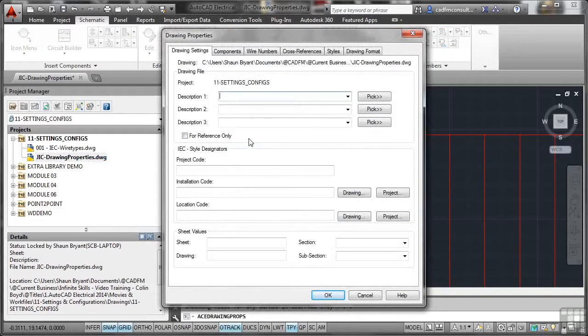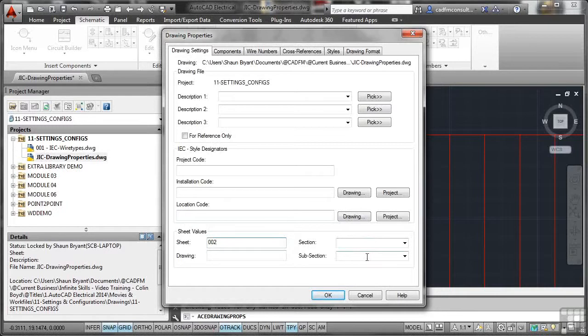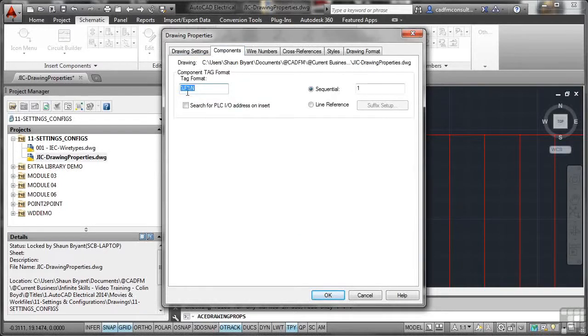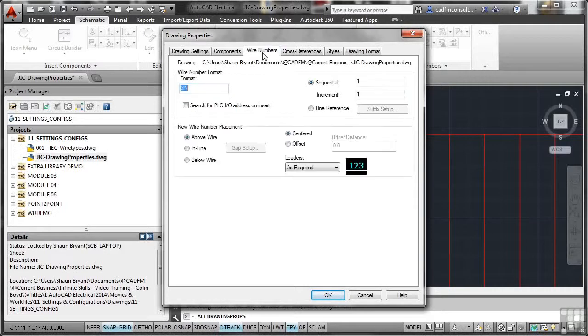In the drawing settings you've got project, description one, description two, project code, installation code, and location code. We'll give it sheet 002 since it's next in the drawing list. Section and subsection are extra descriptor fields for database work. On the components tab, you'll see the component tag format: %f, %n — that's the numbering format, currently sequential starting at 1. I want it to start at 001, so the next component added will be 001, not just 1. The same applies to wire numbering — you can change the wire number format. %N stands for number, so wires will be numbered sequentially starting at 001 with increments of 1, giving 002, 003, and so on.